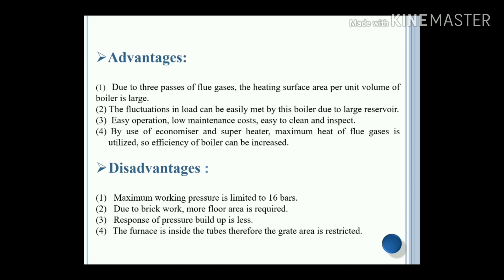Some advantages of the Lancashire boiler: due to the three passes of flue gases, the heating surface area per unit volume of the boiler is large. Fluctuations in load can be easily managed due to the large reservoir. Easy operation, low maintenance cost, easy to clean and inspect. By use of the economizer and superheater, maximum heat from the flue gases is utilized, increasing the efficiency of the boiler.